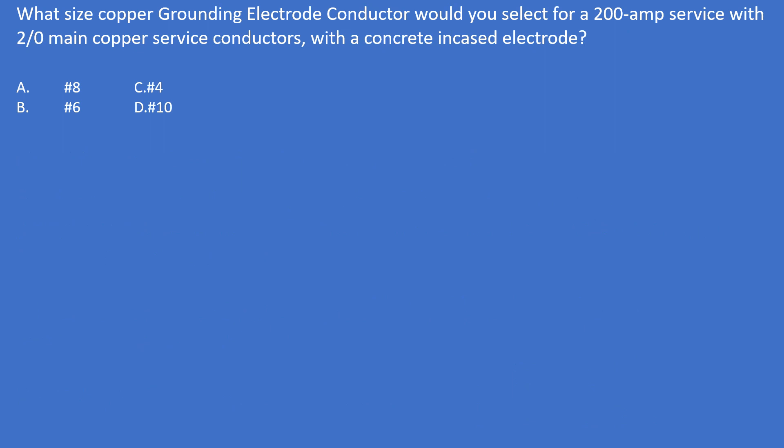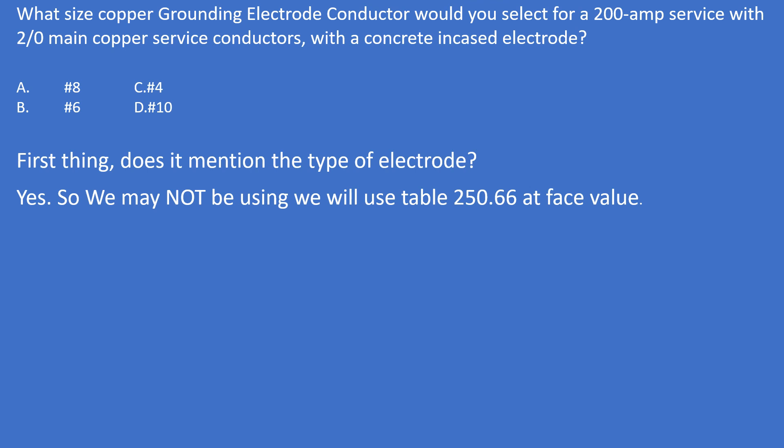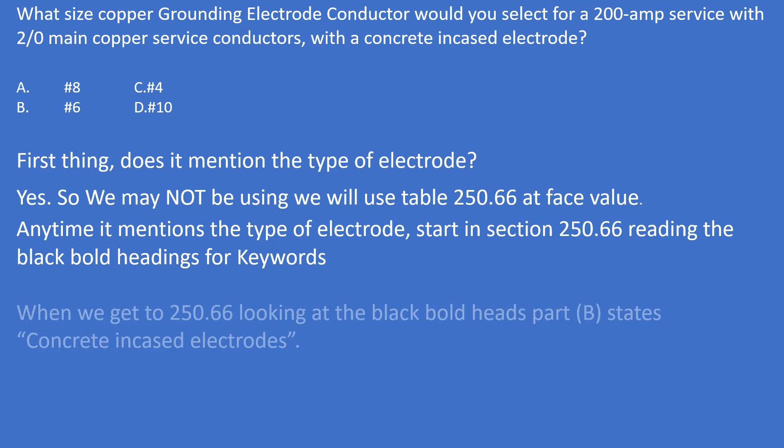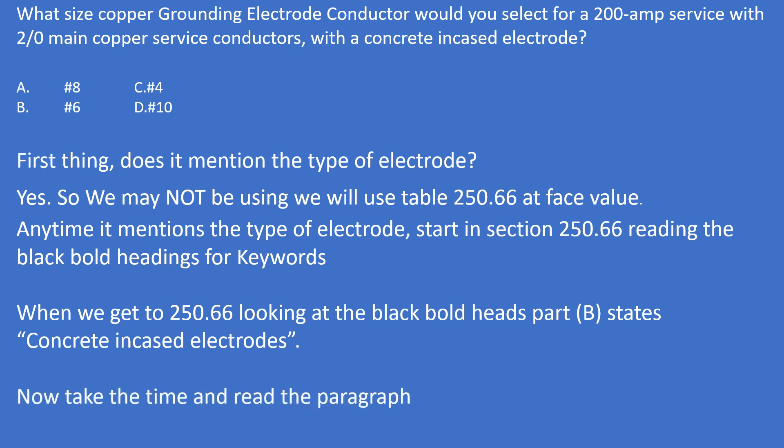Practice problem four: What size copper grounding electrode conductor would you select for a 200-amp service with 2/0 main copper service conductors with a concrete encased electrode? Does it mention the type of electrode? Yes — so check 250.66A, B, or C. Part B mentions 'concrete encased electrode,' so we read that paragraph. It's not required to be larger than number 4 copper, regardless of the main conductor size or overcurrent device amperage — it only has to do with section 250.66B.